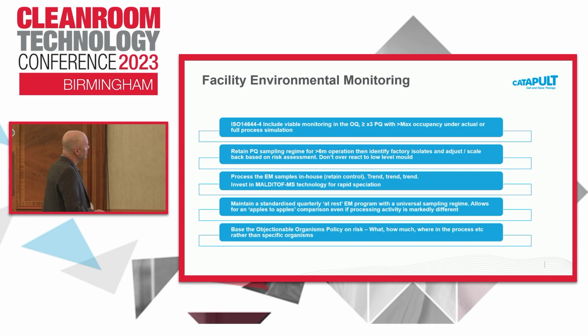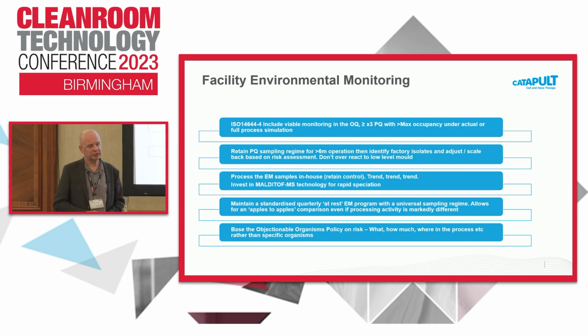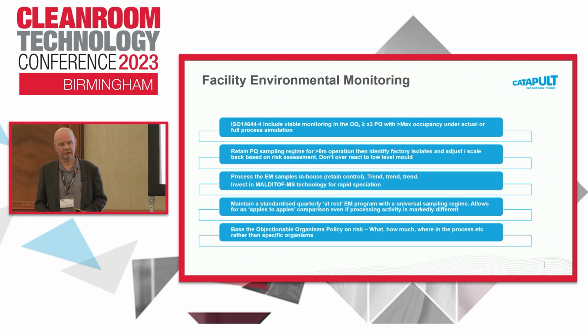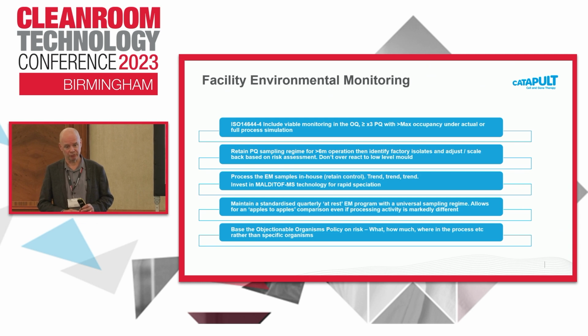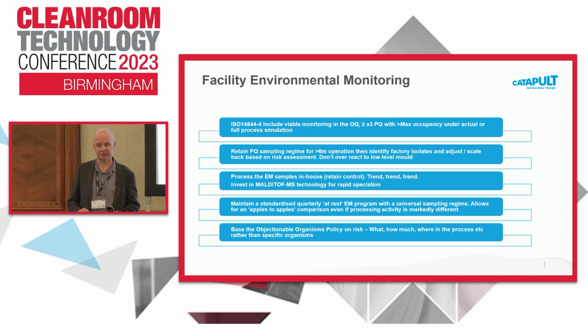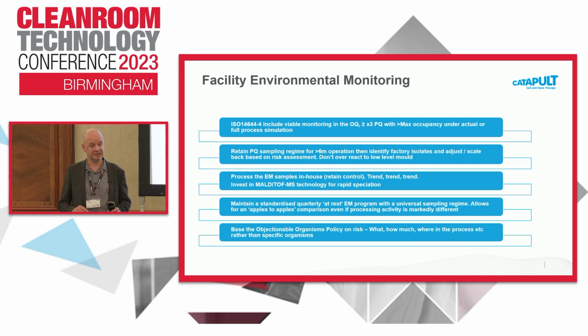Okay. So once you're through a successful PQ, then in our experience we've found it's best to maintain that quite intensive monitoring program for a good 6 months of operation. That allows you to do a number of things. It gives you some really good baseline data. It also allows you, after that period of time, to identify and establish your factory isolates, because you're going to need those for a number of things.